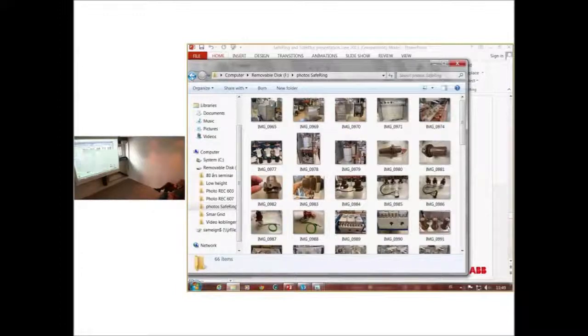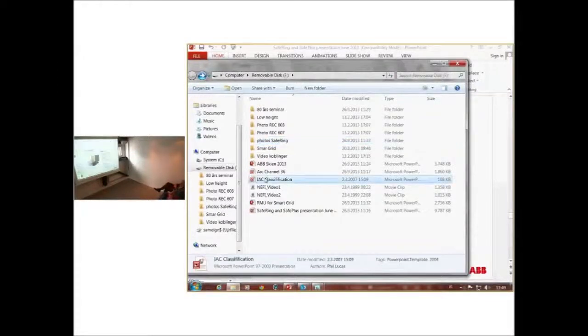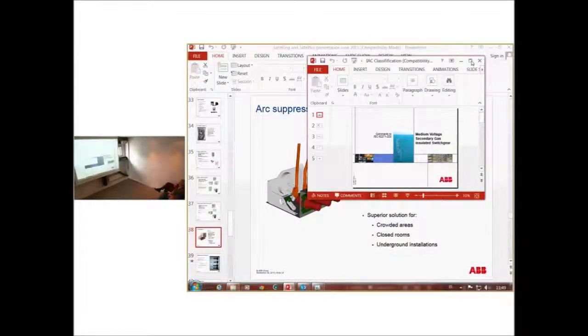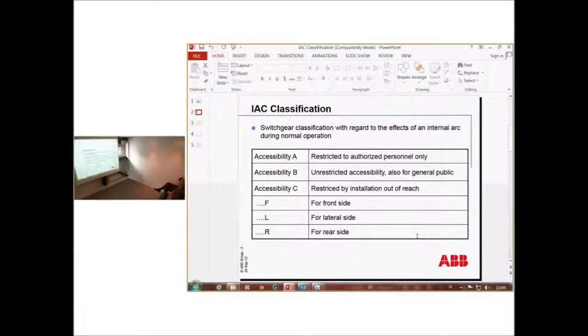The standard is actually an IAC, AFL classification. That is the standard. IAC means internal arc classification, because in the past it was not standardized how to test a switchgear, but now this IEC norm made a rule. Firstly, internal arc classification, that is arc inside the switchgear. And you can ignite it inside the bus bar, but also in the cable compartment.